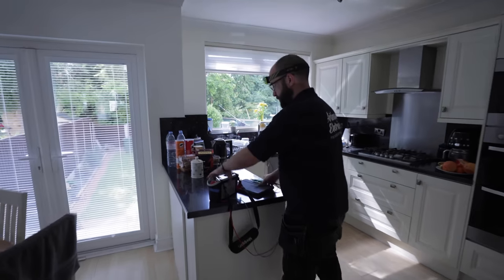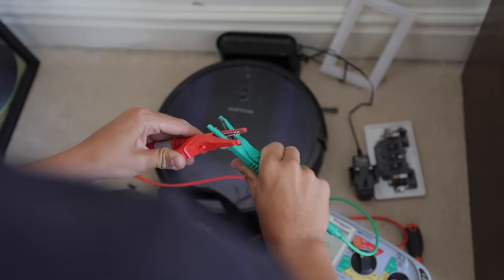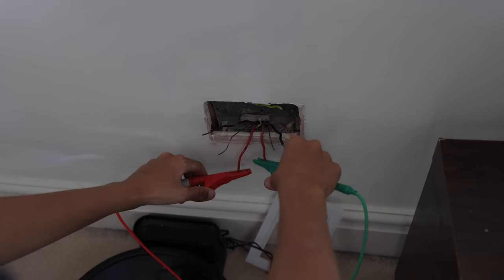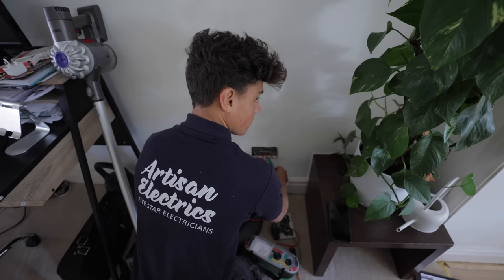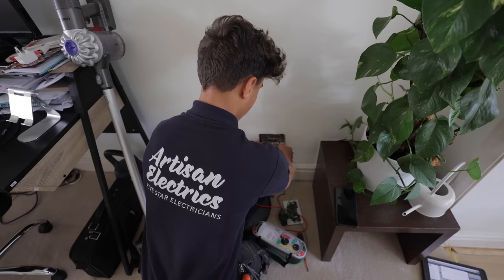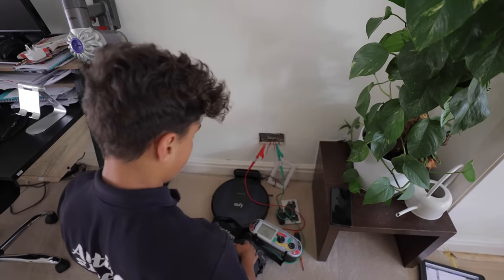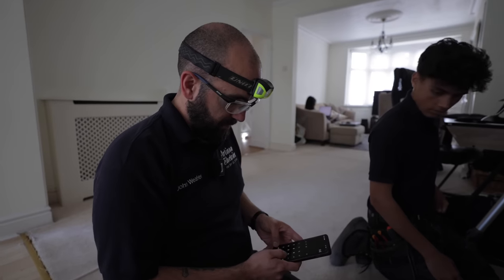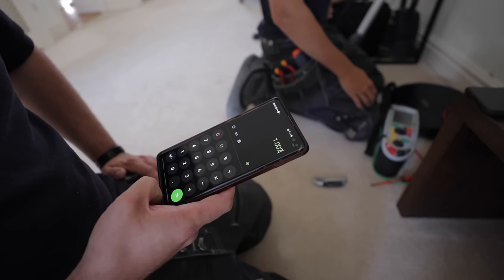16 points. If you want to null them first — should be zero to be honest, my tester's done me quite good. Watch it make me look like a liar now. Oh, see — spot on. Nice. 0.6... 0.6... 0.85. Hold the probes and let go so it settles because your hands won't actually move. It's not settling nicely, but let's do a little calculation: 0.6 times 1.67 should be looking about the one mark — oh nice, looking pretty good, not bad.